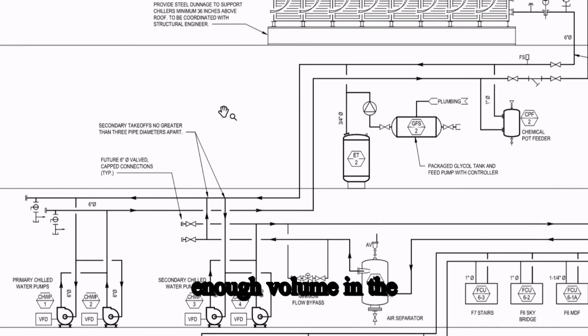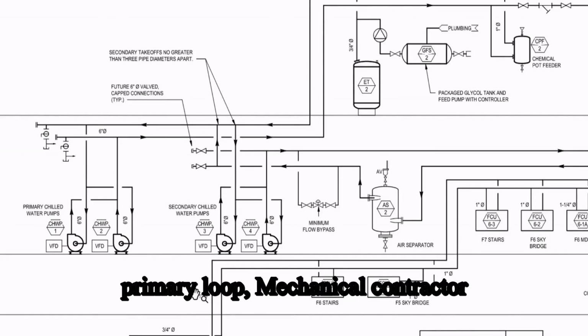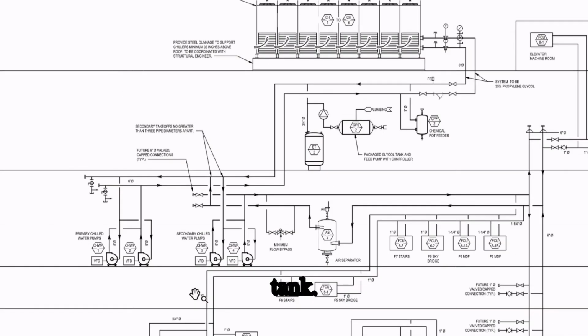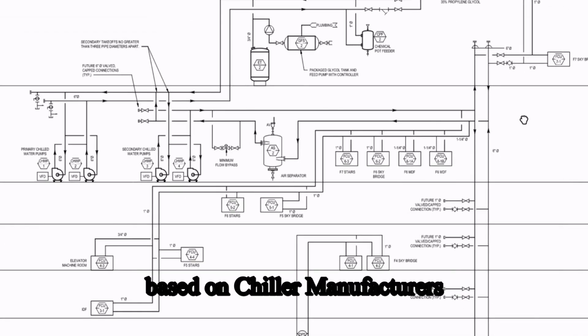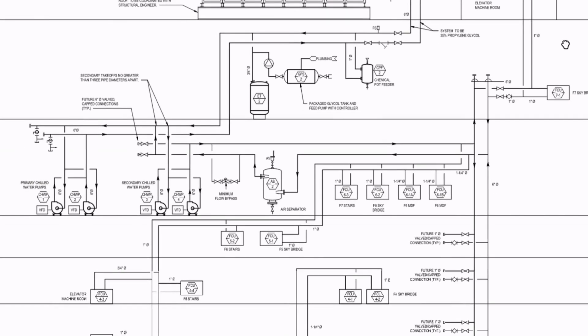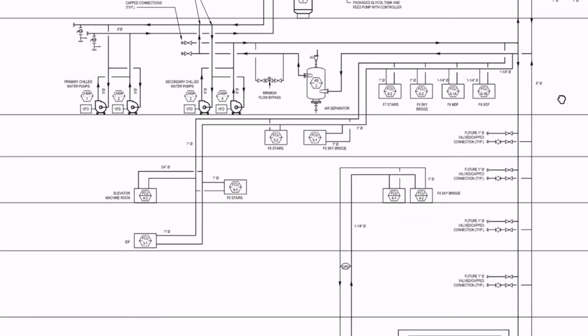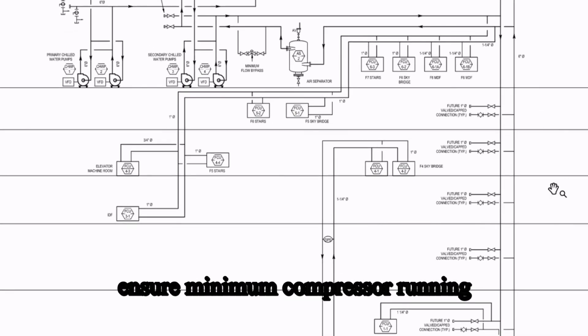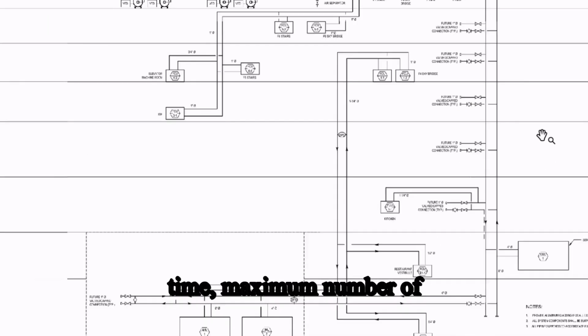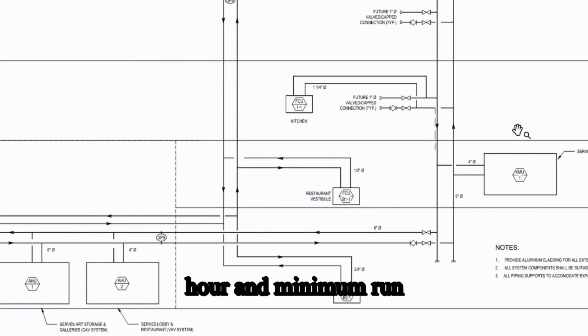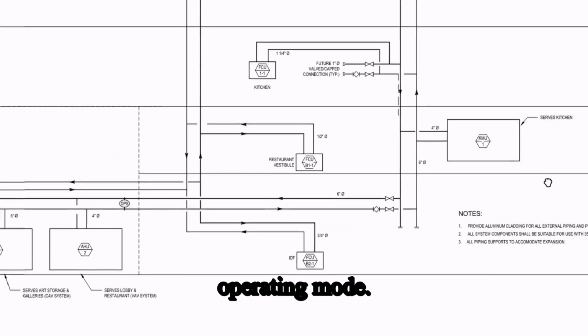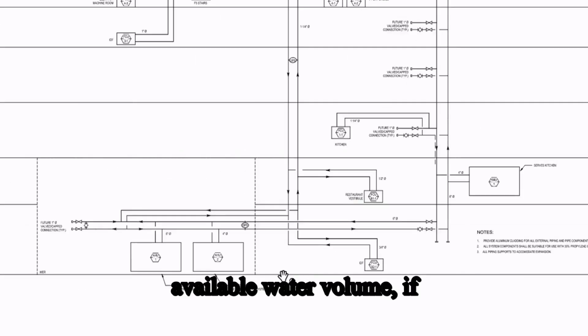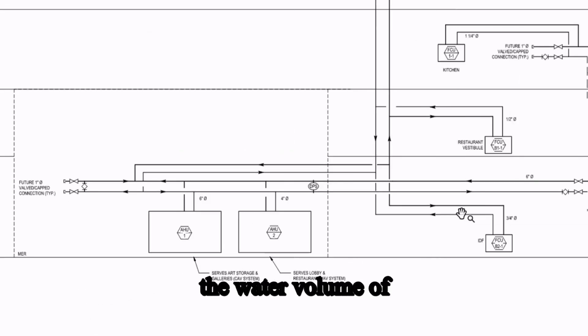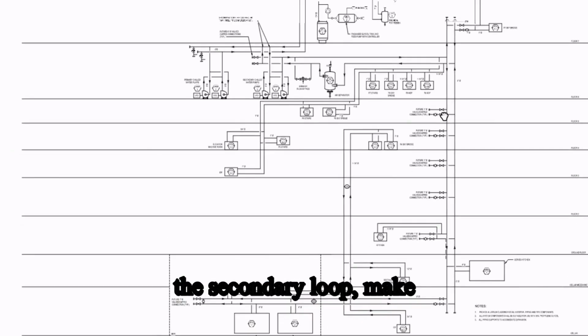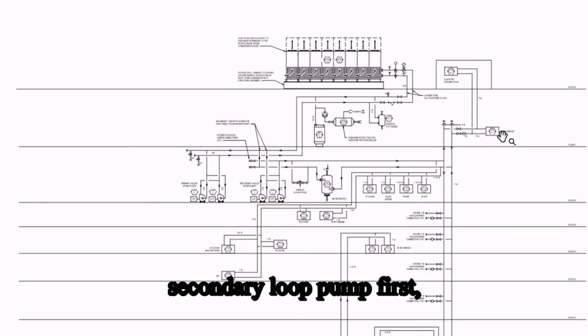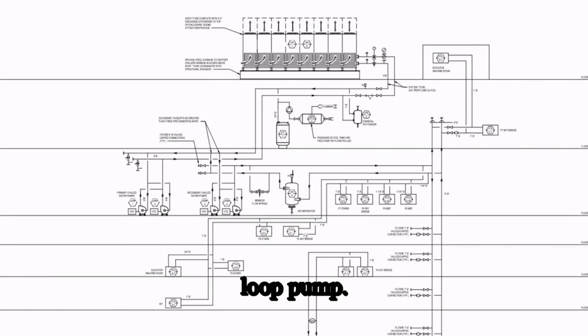If there is not enough volume in the primary loop, the mechanical contractor should install a buffer tank. The size of the buffer tank should be based on the chiller manufacturer's suggestions. Respect water volume recommendations from the chiller manufacturer to ensure minimum compressor running time, maximum number of compressor starts in an hour, and minimum runtime for the assigned operating mode. During calculation of the available water volume, if you want to consider the water volume of the secondary loop, make sure you always run the secondary loop pump first, then start the primary loop pump.